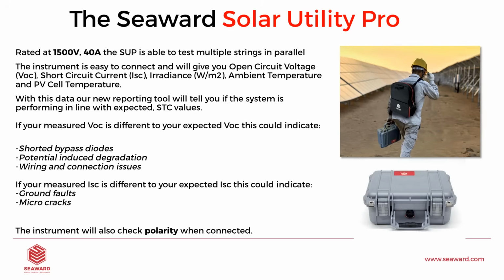It's housed in a Pelican case. It's very rugged. It is an official Pelican case. We didn't use any kind of fake. And the instrument is very easy to connect, both in the combiner and at a string level. It will give you open circuit voltage, short circuit current, irradiance, ambient temperature, and cell temperature.